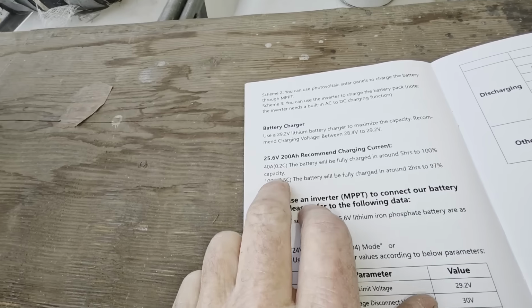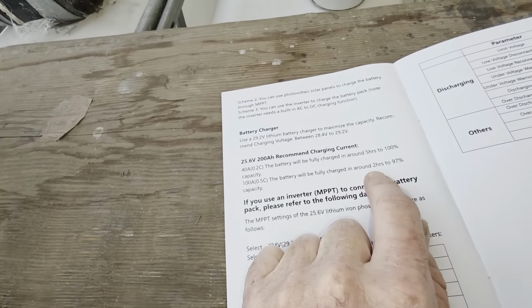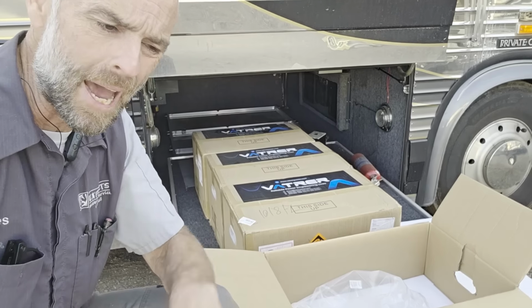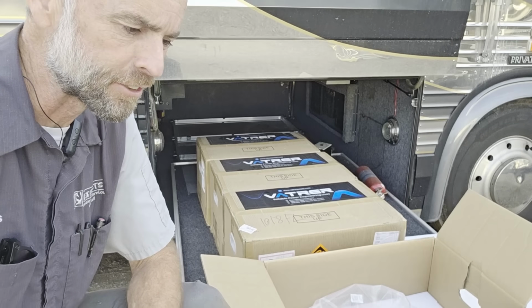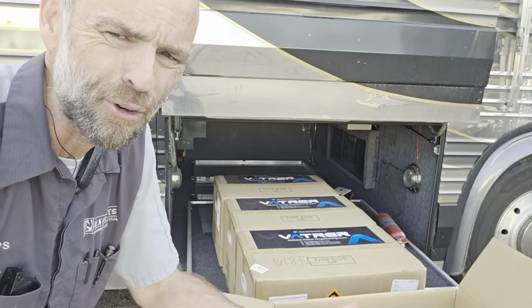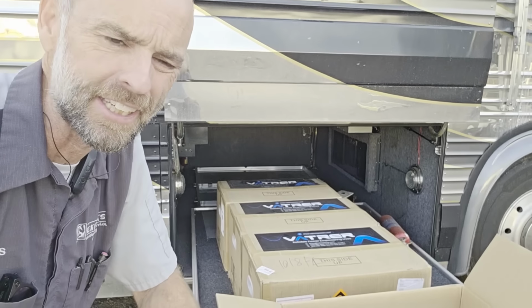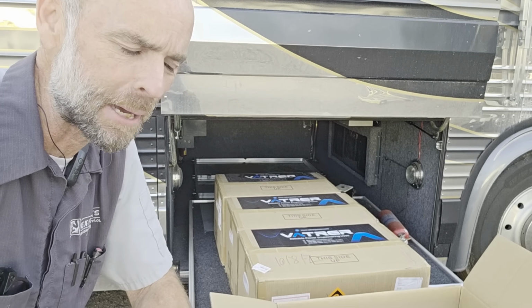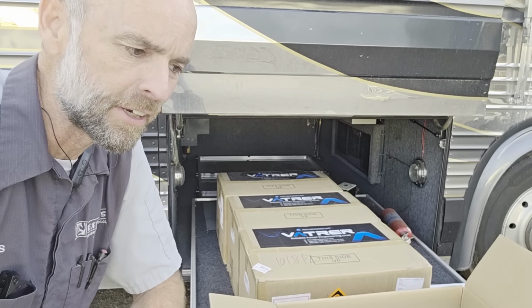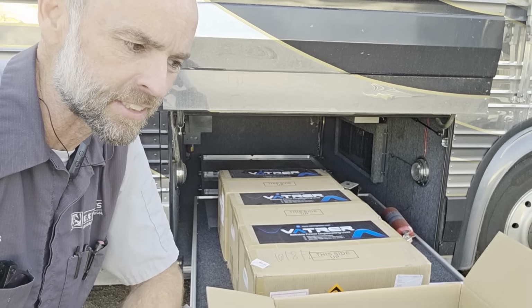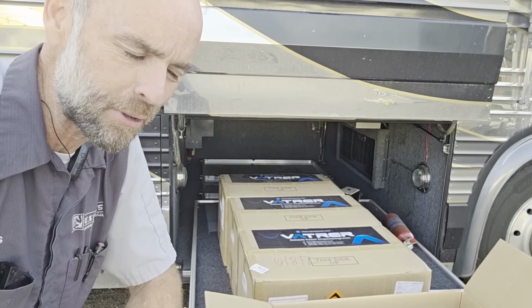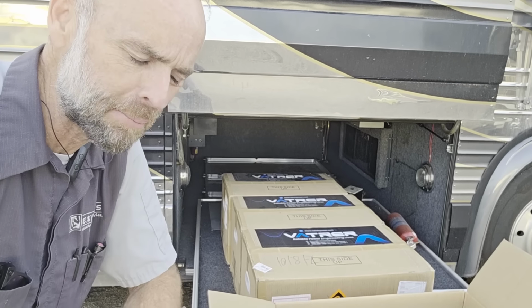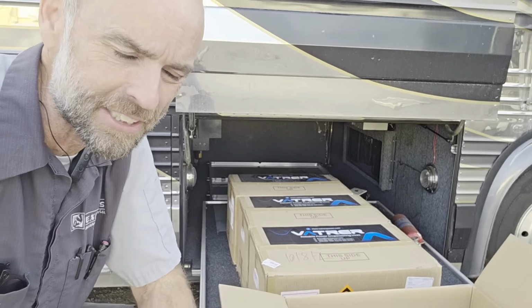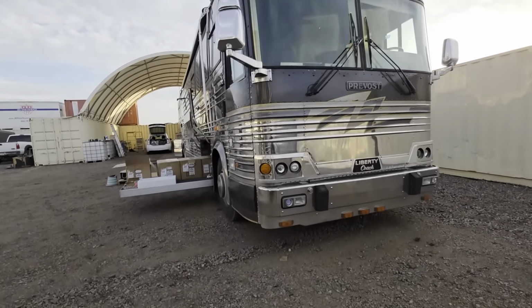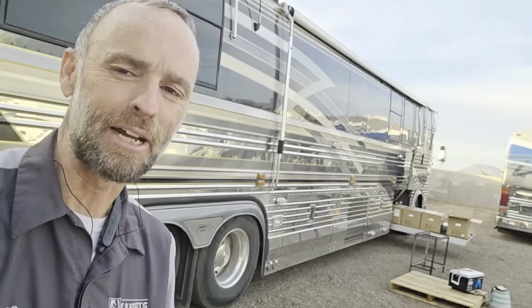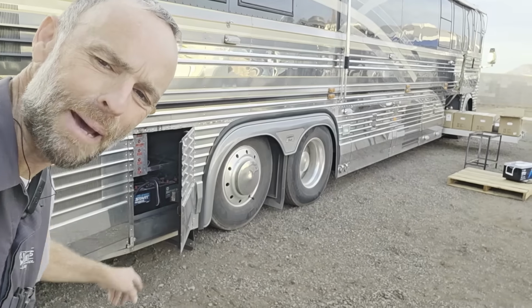But of course, if you have a 200 amp battery charger, you can get it charged up fully in an hour. Now, in fairness, with 4 batteries, even with a 200 amp charger on there, it will still take, what, 4 hours? Math is somewhere around there, so 4 or 5 hours to get a lot of battery capacity put back up again, because we have 4 5100 watt hours of power available to us. So that's 20 kilowatt hours of battery power being charged back up again in 4 or 5 hours, which is pretty impressive, and a lot better than Liberty Bus would have ever thought that we'd get, or that this elegant lady would ever see, let alone be able to fit in that small little battery compartment right there.